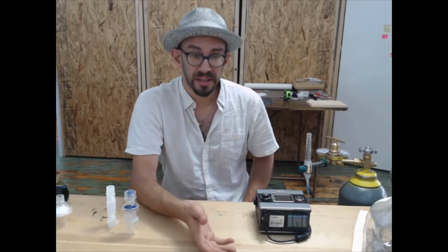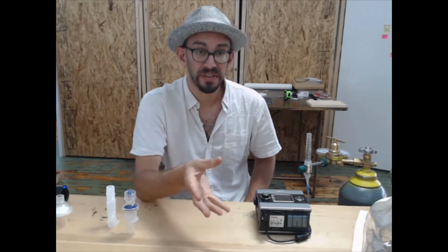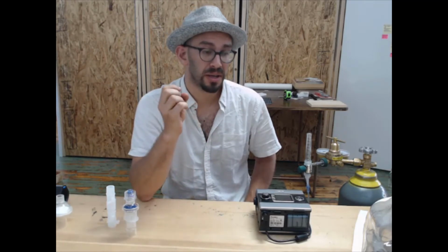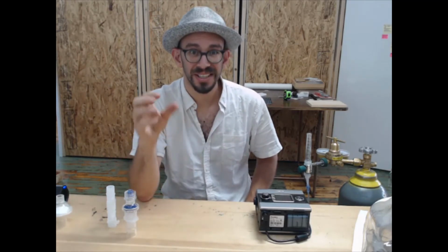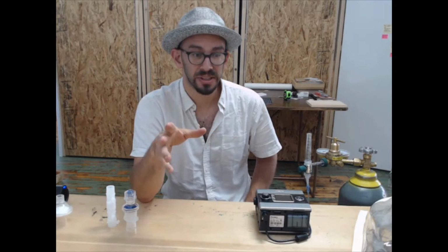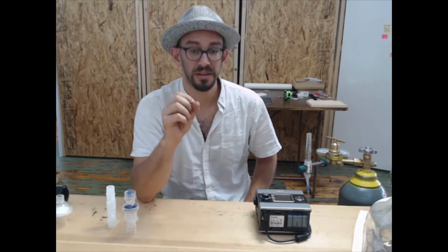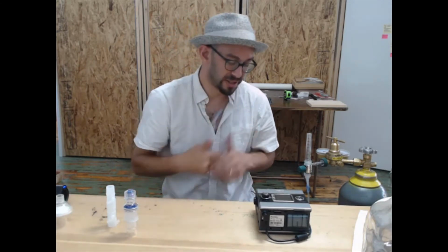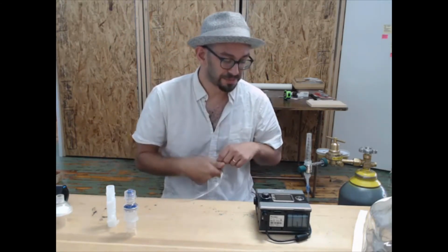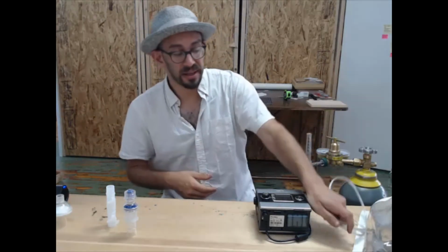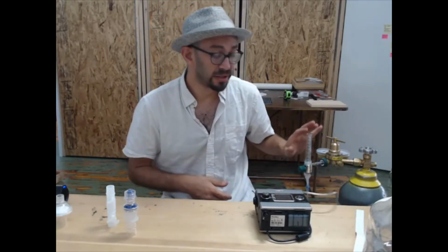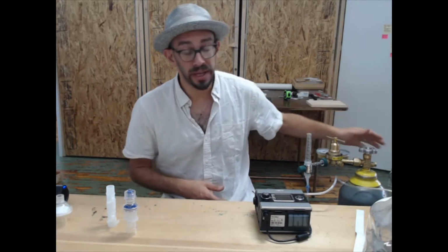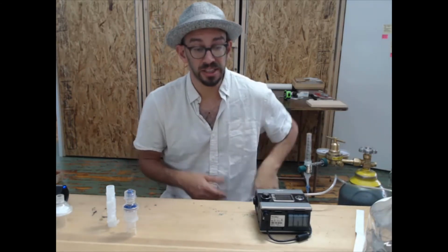If you can get a regulator that can achieve at least 35 liters a minute, everything gets easier because you are not combining multiple tanks to get higher oxygen flows. You can work with one tank, your logistics are simpler, your settings are simpler, and the opportunity for error is much less. I really recommend, if at all possible, you find a high flow regulator and ensure that you have sufficient supply of oxygen in your hospital.